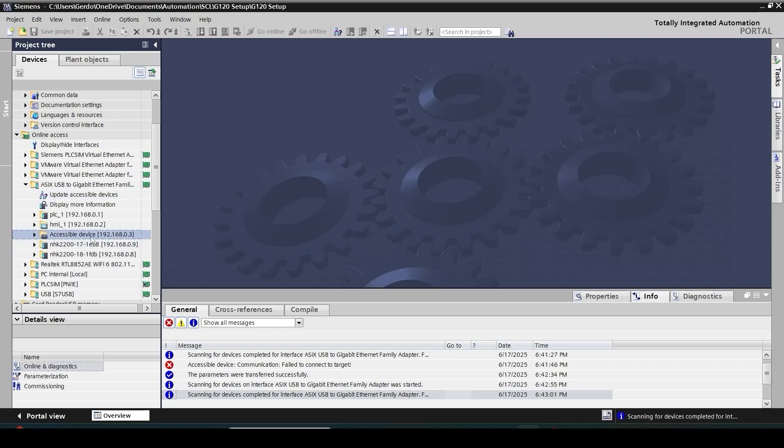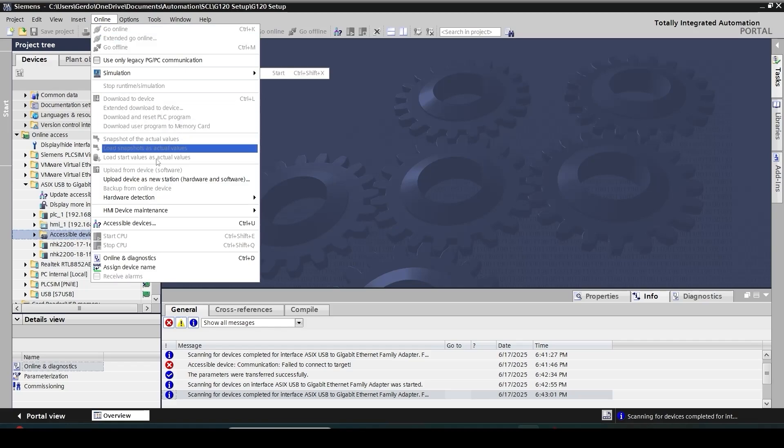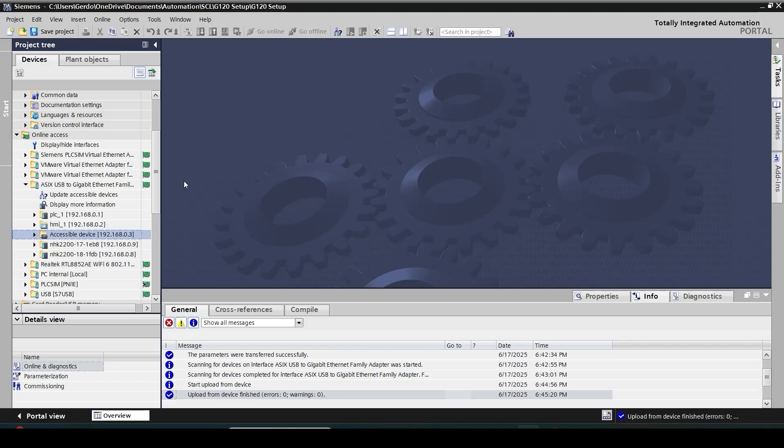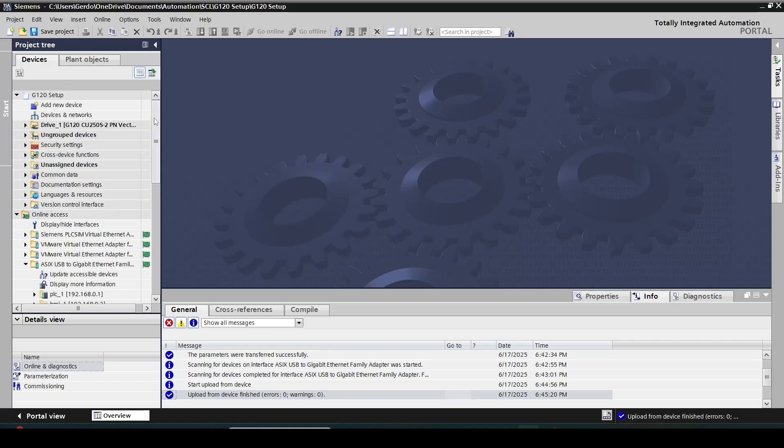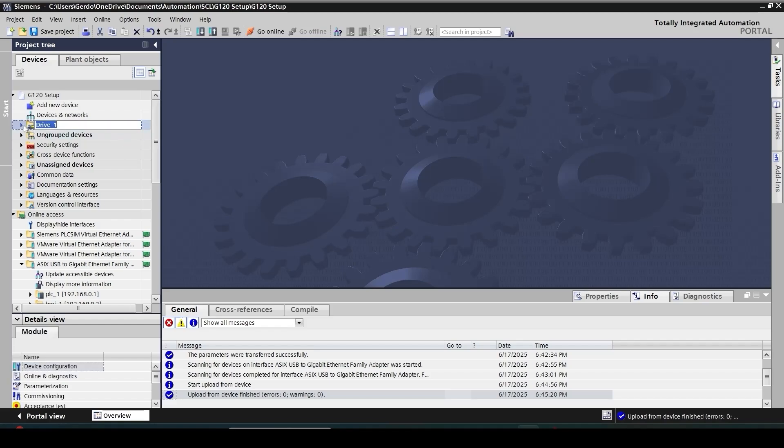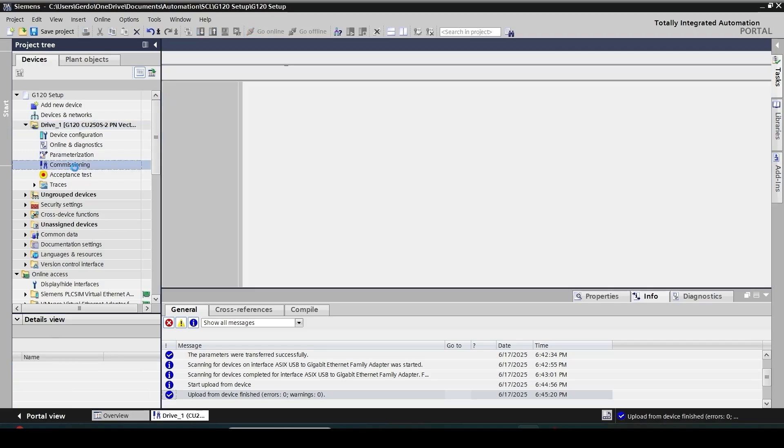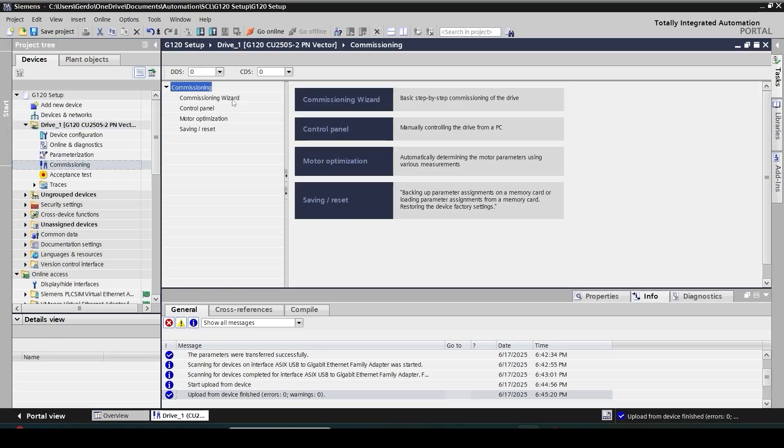Next step is to select this object and then from the online menu click on upload device as a new station. Why I'm doing this is it's going to create a driver station that is fully aligned with the existing module and I don't need to be worried about part number, version and all the other details that sometimes are very frustrating within the Siemens work. Now I can see a drive object has been added to my project. Underneath this drive object there's a section for commissioning, so I'm going to use commissioning wizard that takes me through the necessary steps to get the drive up and running.